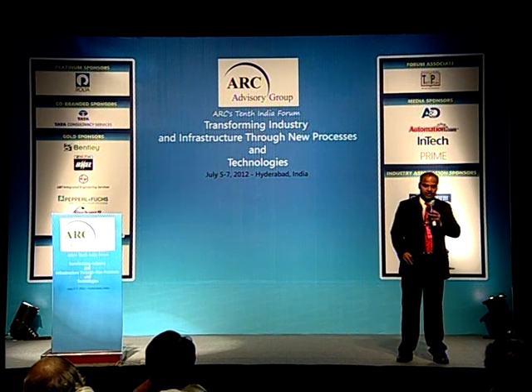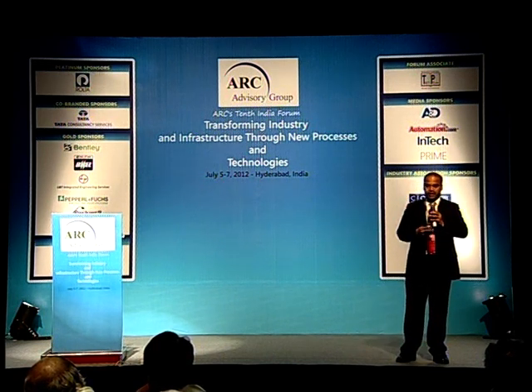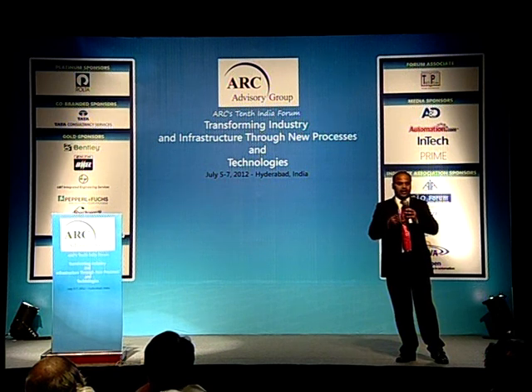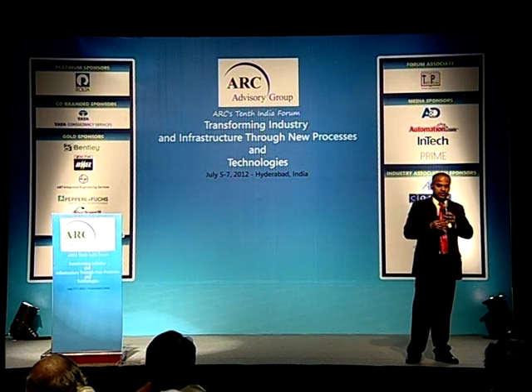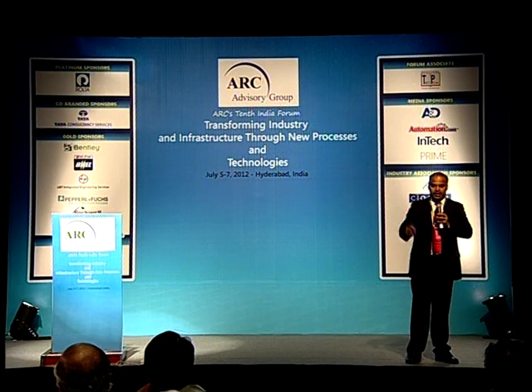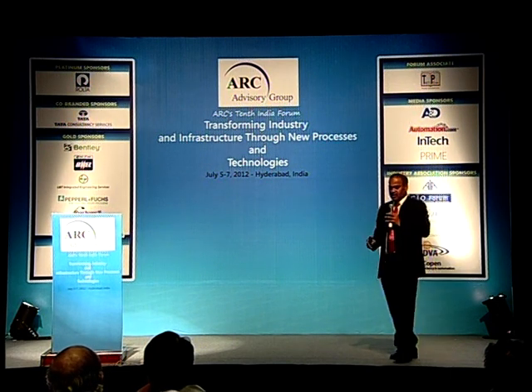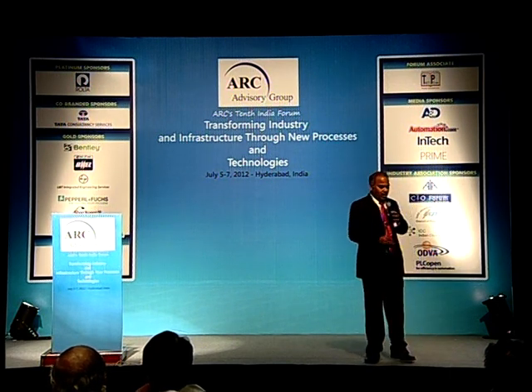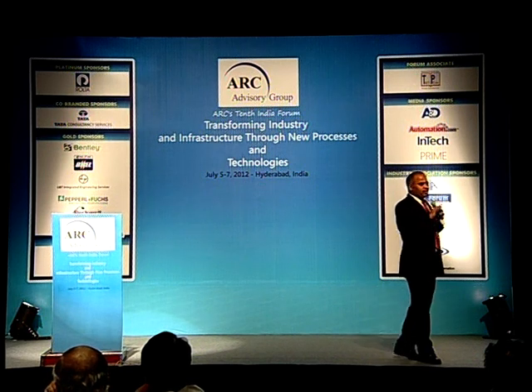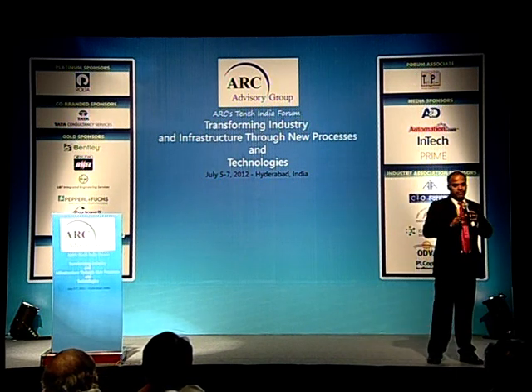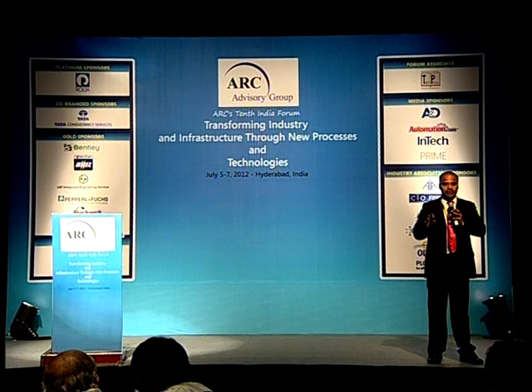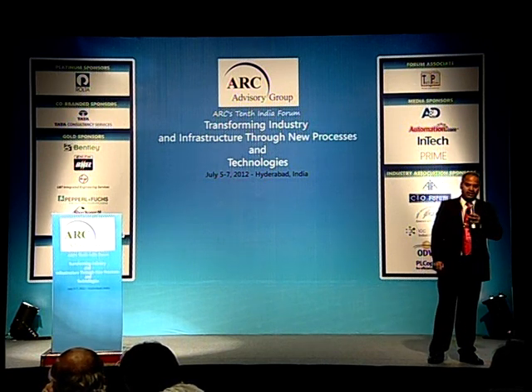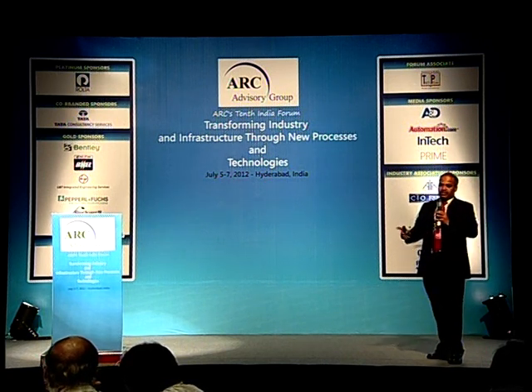We have a DCS IO card, and then we have one transmitter, and that's going to power a single device. Even if we limit the energy in the control room, the energy that is going to be applied in the hazardous area is more than sufficient to drive a single device. But this brings a problem when we move into digital applications. When we are moving from conventional to digital, we are not going to connect one single device to the DCS.